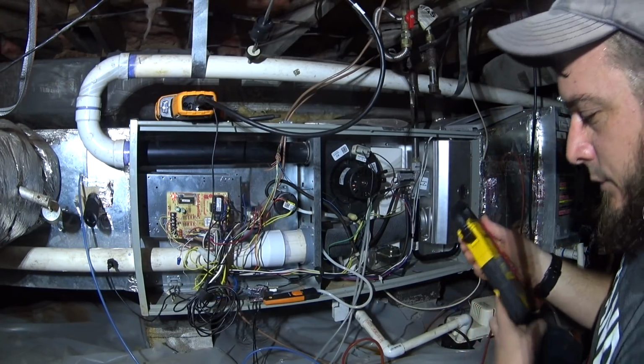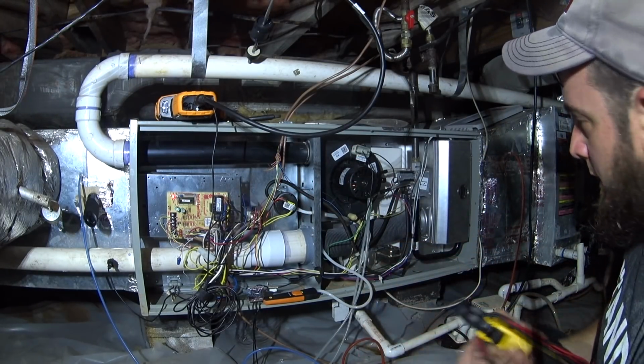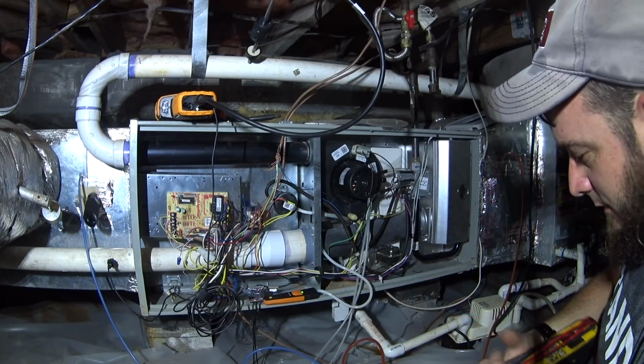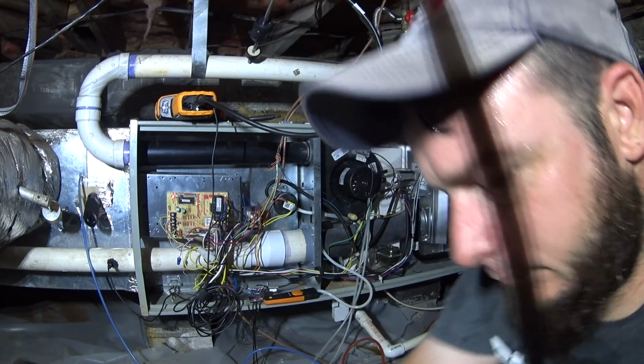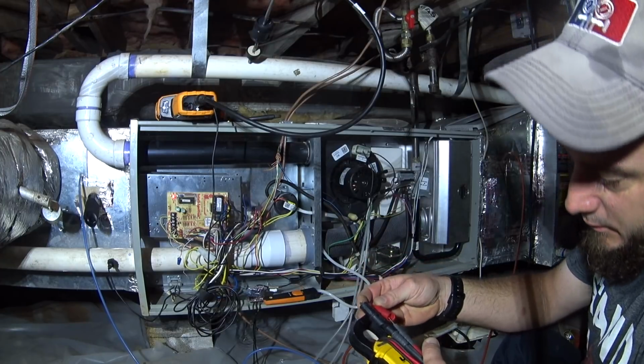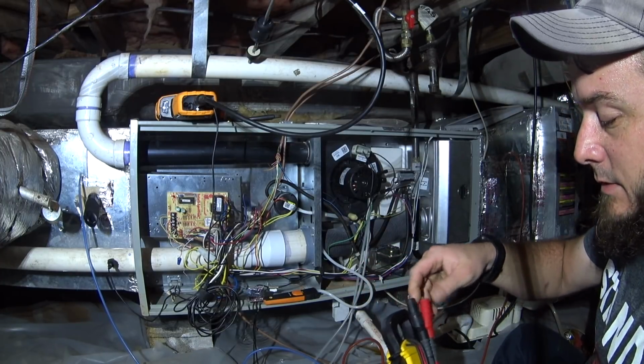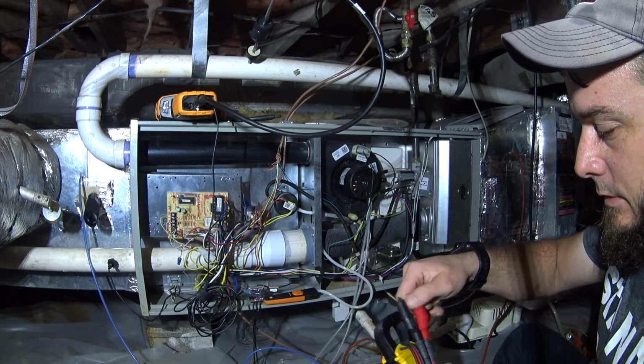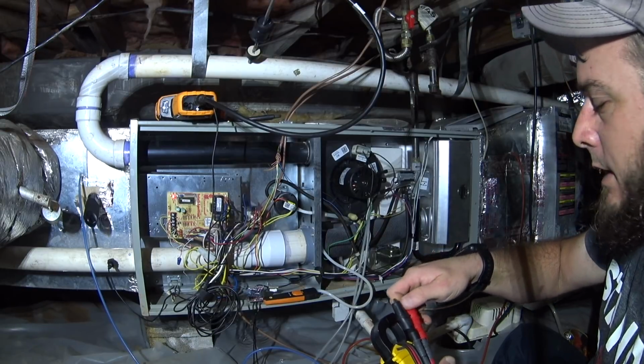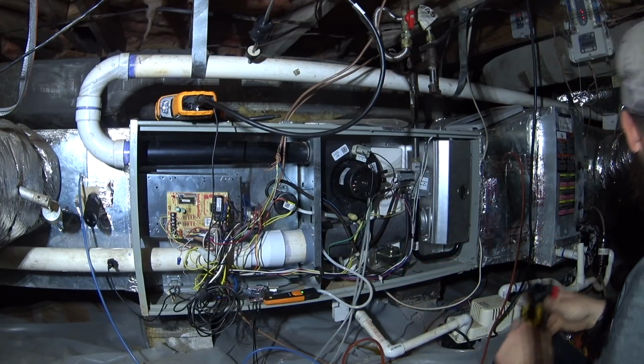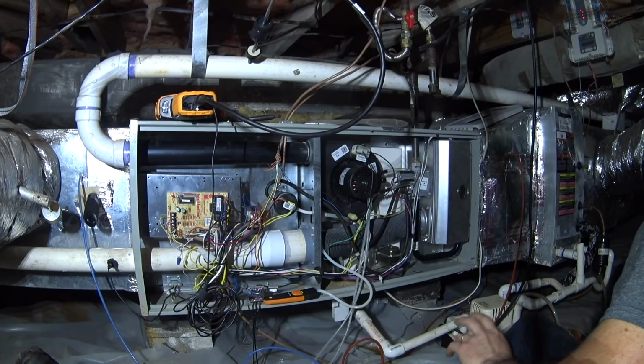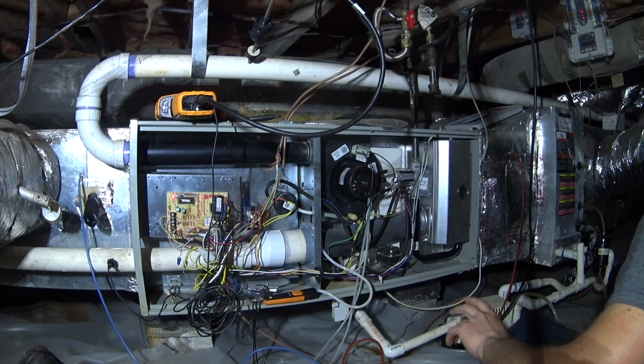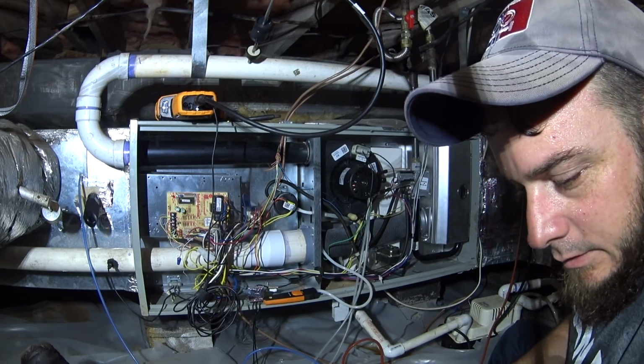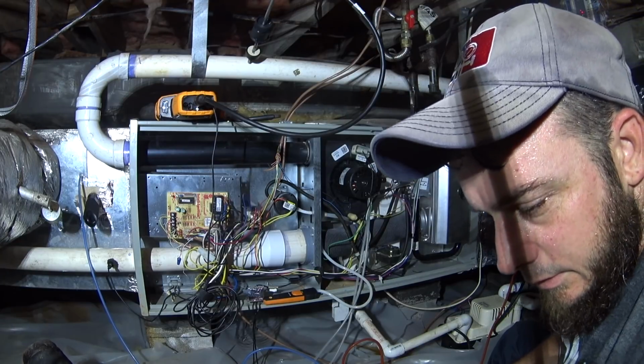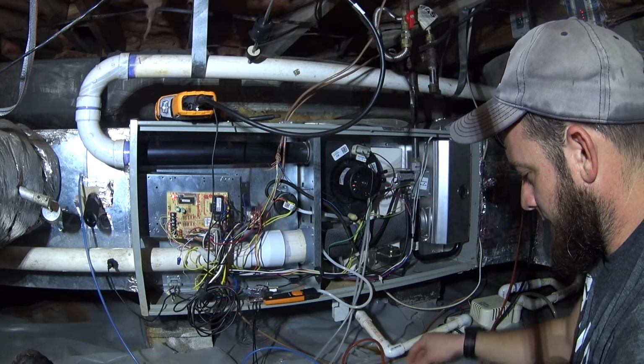and now we're just waiting for temperature split. Now, just for instance, if I was trying to troubleshoot a flame sensor potential issue, I would leave that burner box open so that I could maintain my meter connections and be able to monitor what the flame sensor does over time. But generally speaking, as long as you're not experiencing an issue, you don't need to concern yourself with monitoring the flame sensor over time.